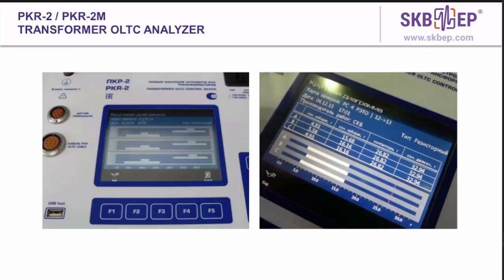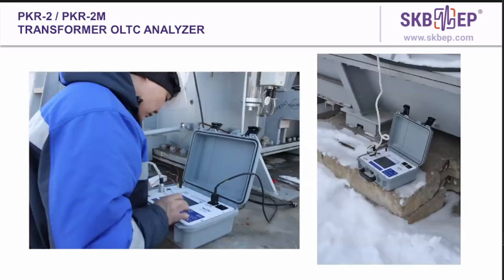Here is an example of the circular diagrams on the instrument display. On the left is a circular diagram of the OLTC reactor type recorded across 3 phases. On the right, there is a circular diagram of the OLTC resistor type. These pictures were taken during some tests of the device at one Russian substation.